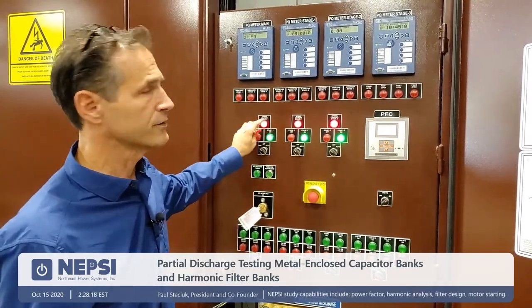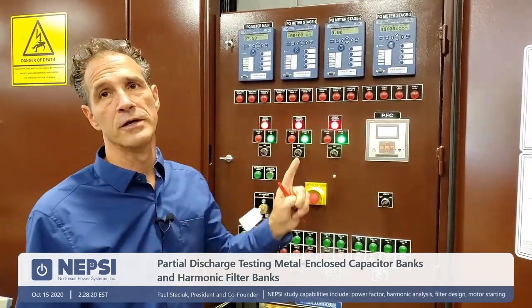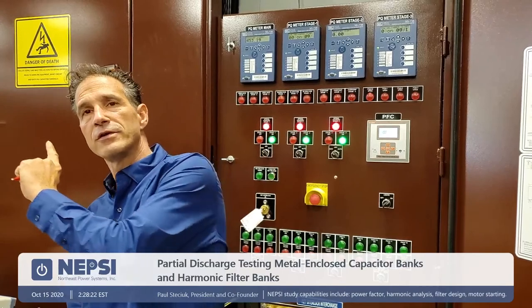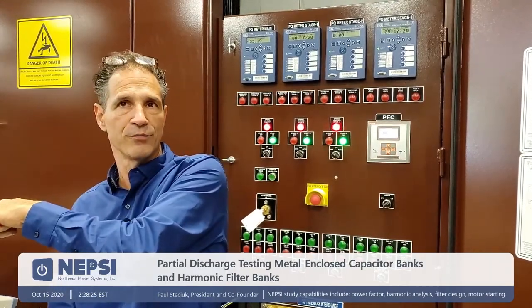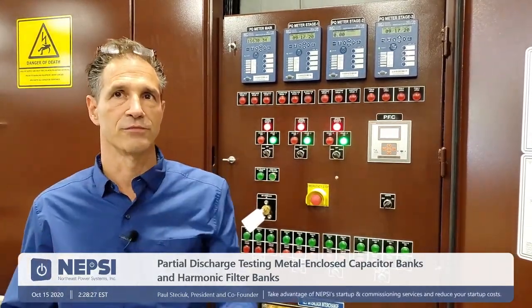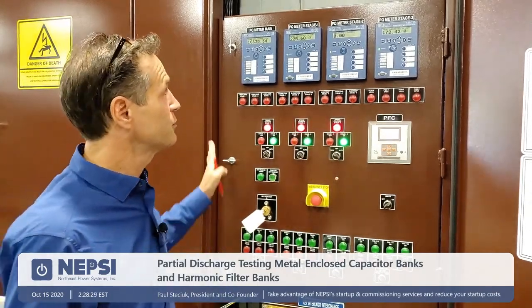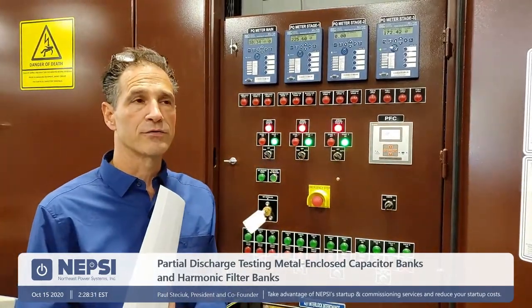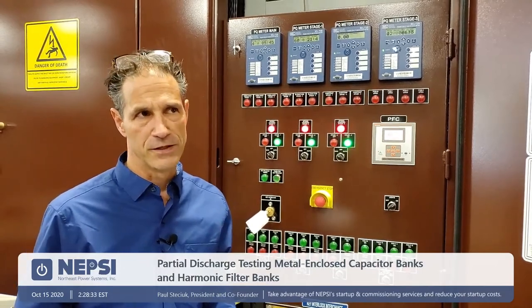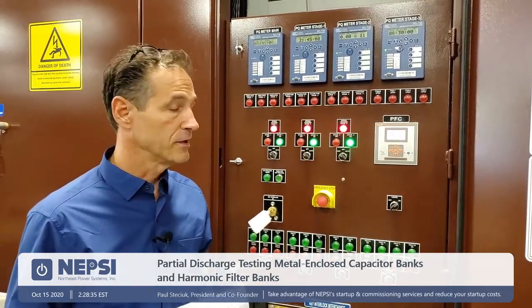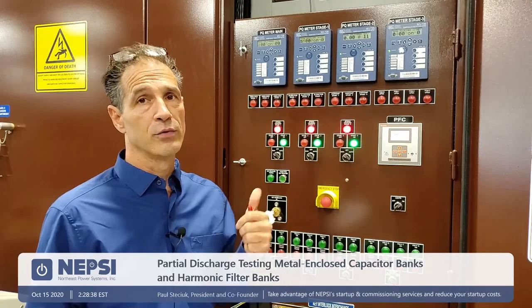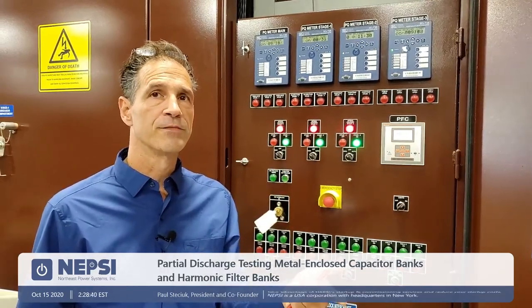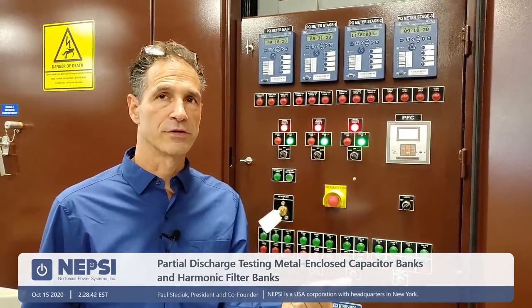No, closed position, I'm sorry. In the closed position, and everything's in the circuit except for the capacitors. We cannot test with the capacitors in, it's just too much capacitance. So this is the way we set up the equipment. We take the lightning arresters out. PTs are out. And everything else is in. So we will ground two phases and keep one phase in. We do the test three times.